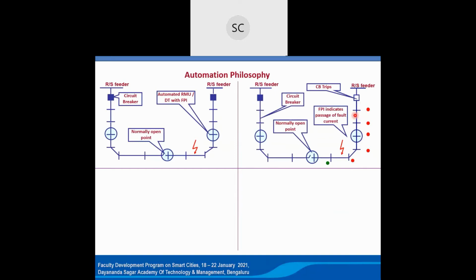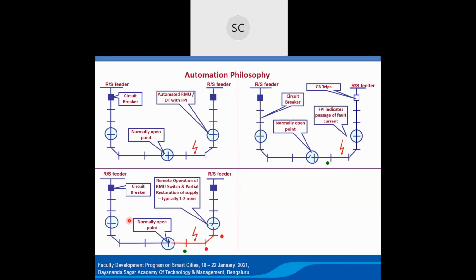So it will indicate that this particular breaker has tripped and this line is having a problem, and these fault passage indicators are glowing, and that indication goes to the control center. By the time the crew comes, we can see here immediately, based on decisions at the control center, either we can automate or with DMS assistance.